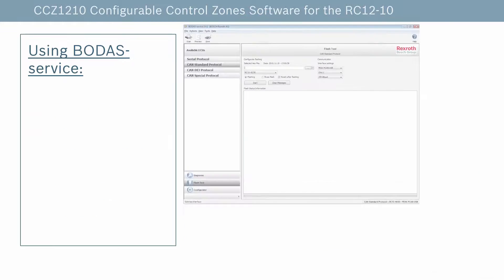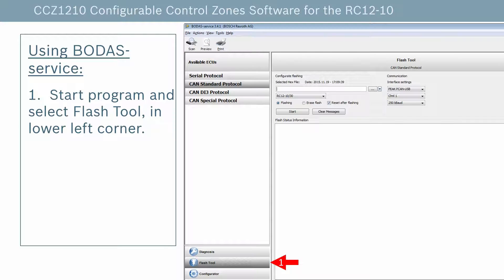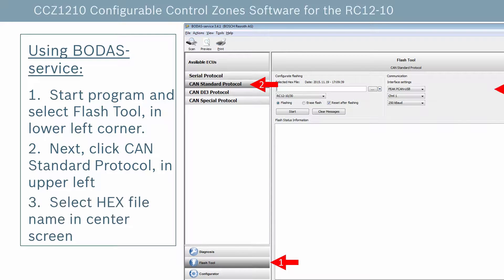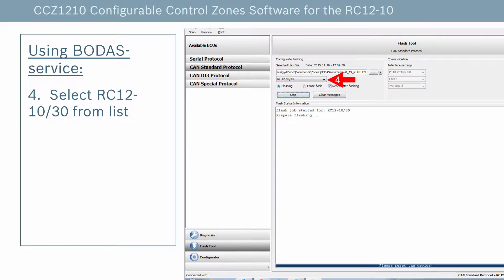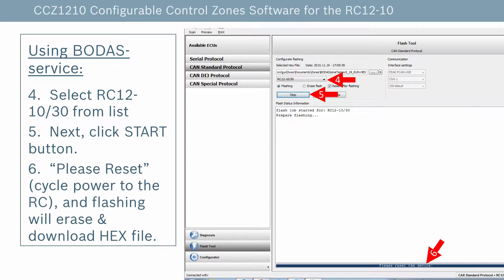Flashing the Zones software into the controller is a simple process. First, select the Flash tool in the lower left corner. Second, select the CAN standard protocol in the upper left corner. Third, browse and select the hex file for the Zones software. Fourth, select the RC-1210 controller in the drop-down list. Fifth, click the Start button to begin the flashing process. And lastly, cycle the power to the machine before the blue bar at the bottom disappears to the left.